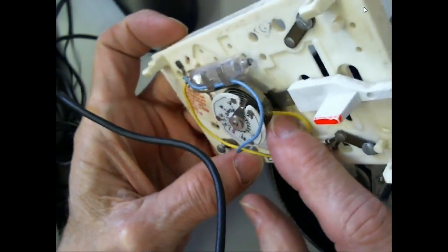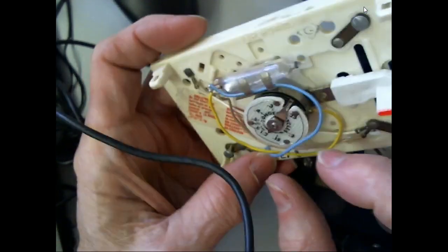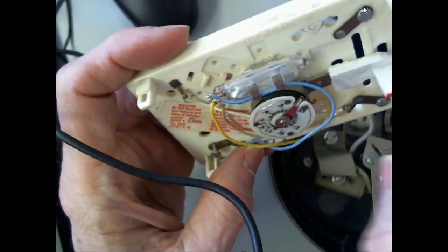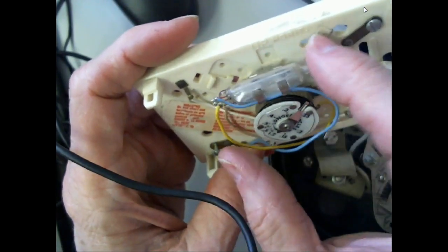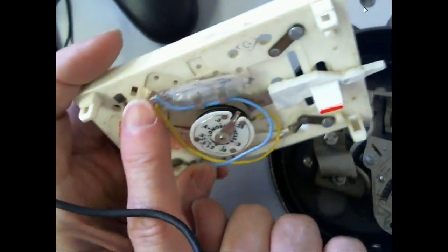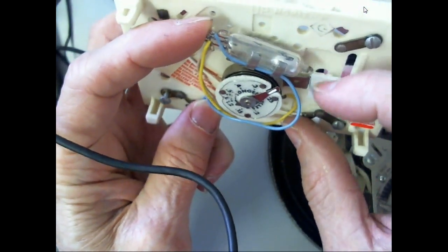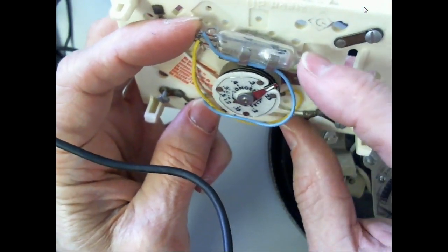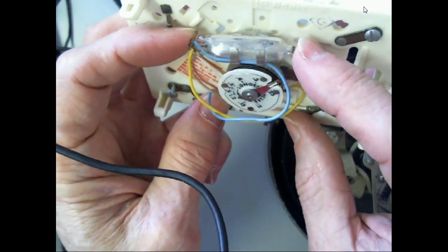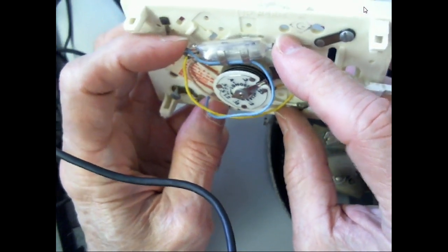So this is a bimetallic strip. It's in a spring. And so when it heated, it would cool down. It would go into a tighter circle and cause us to tilt, or it would go this way. So this way, that would be an open circuit. And I don't know if you can see the wires coming in back here. So this is my contacts. So when the bimetallic strip got to a certain temperature, then the mercury would fall over and cover those two contacts and would turn on my heat.